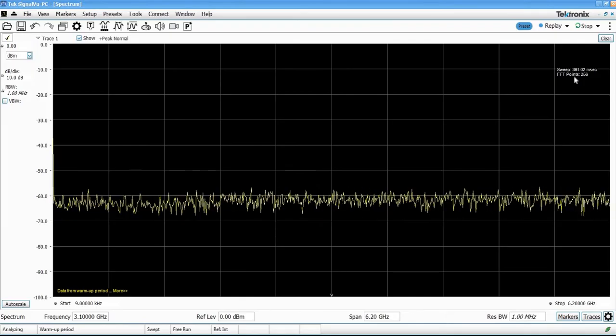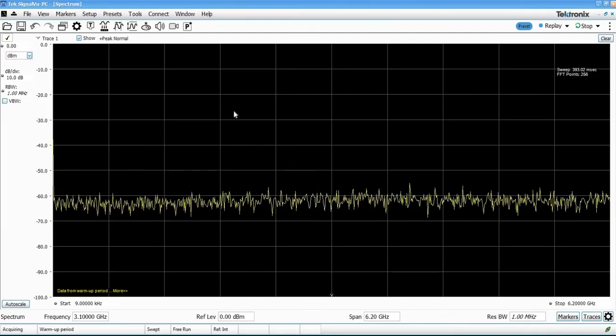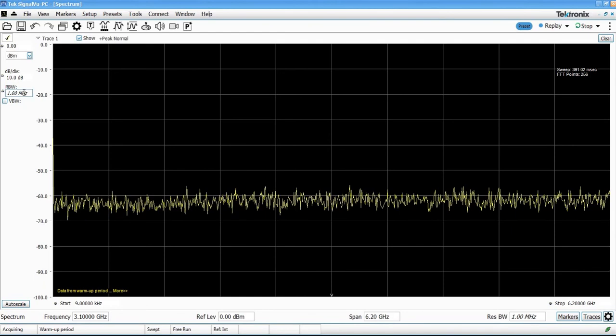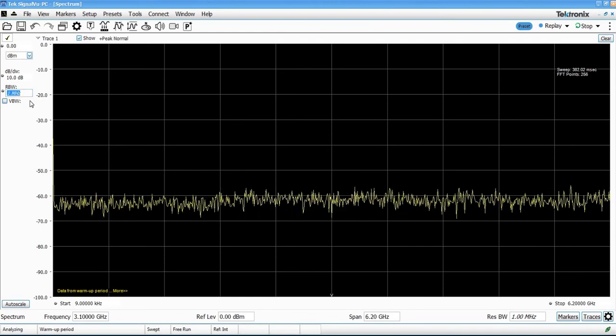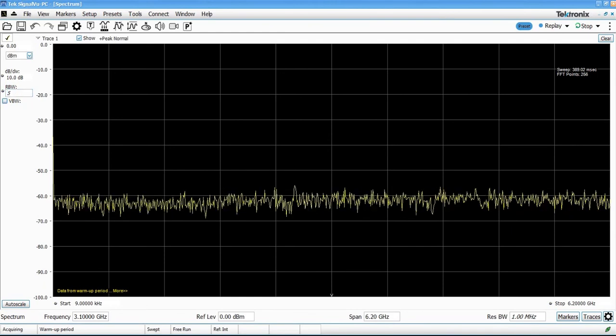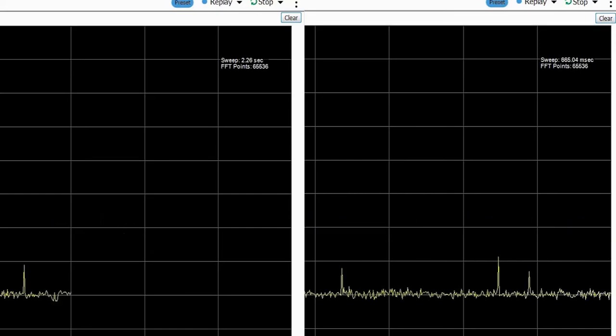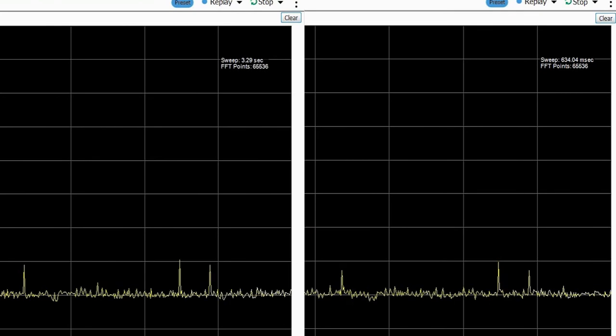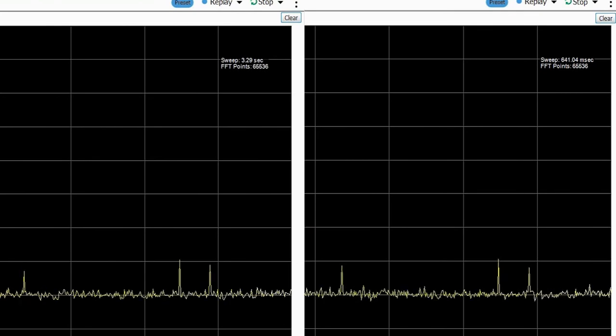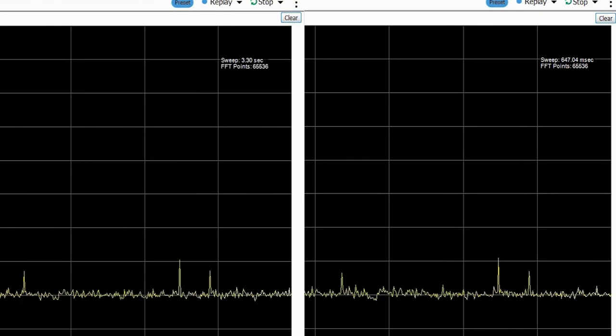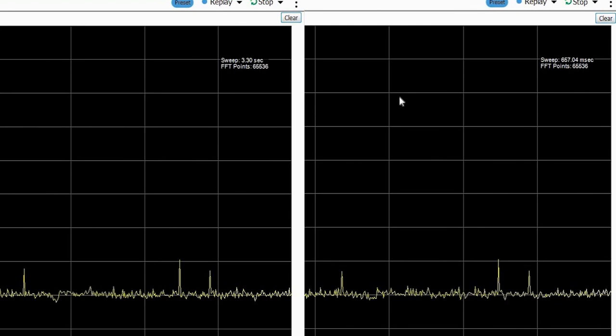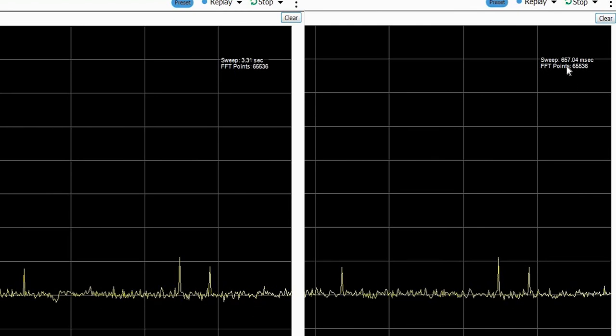Let's reduce the resolution bandwidth down to that same 5 kilohertz for our other point of comparison. And that measurement, if you recall, was about 3.3 seconds to do the sweep. And here we're doing it in about 650 milliseconds.